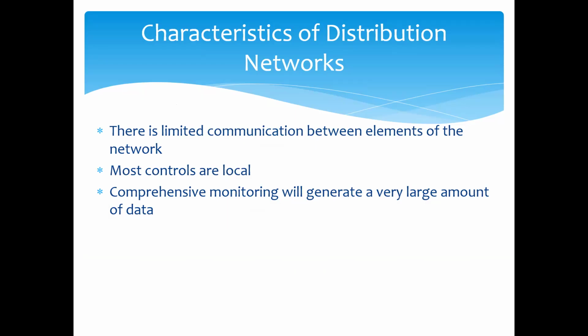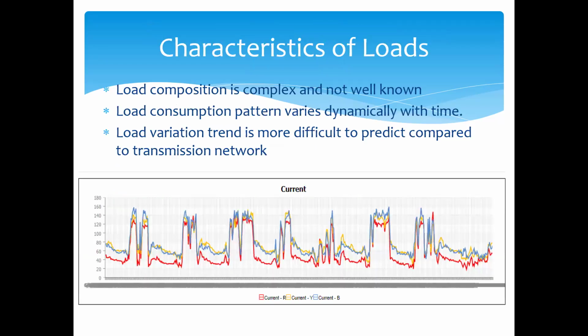There's limited communication between elements of the network, and most controls are local. If we consider comprehensive monitoring, it will generate a very large amount of data because the network is massive. When we consider the load consumption of a distribution network, it's complex and not well known. The load consumption pattern varies dynamically with time, and the load variation trend is more difficult to predict compared to the transmission network.